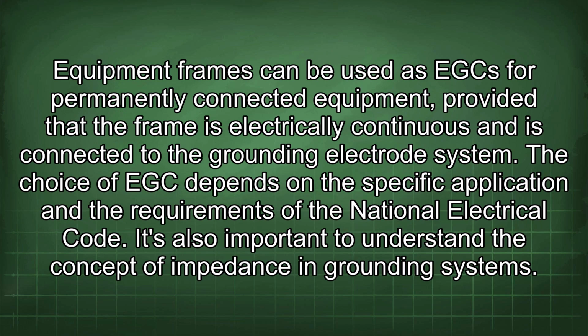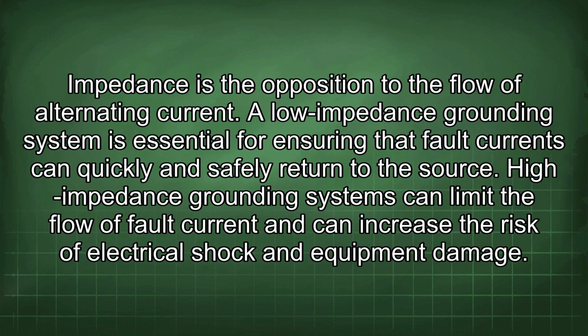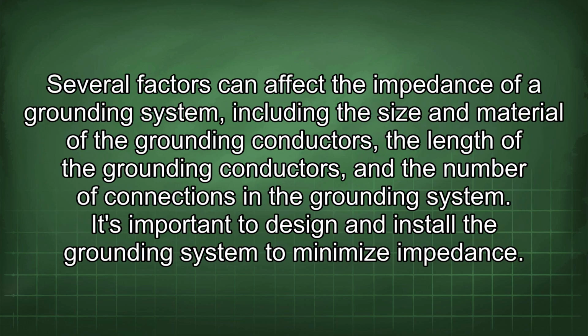It's also important to understand the concept of impedance in grounding systems. Impedance is the opposition to the flow of alternating current. A low impedance grounding system is essential for ensuring that fault currents can quickly and safely return to the source. High impedance grounding systems can limit the flow of fault current and can increase the risk of electrical shock and equipment damage. Several factors can affect the impedance of a grounding system, including the size and material of the grounding conductors, the length of the grounding conductors, and the number of connections in the grounding system. It's important to design and install the grounding system to minimize impedance.